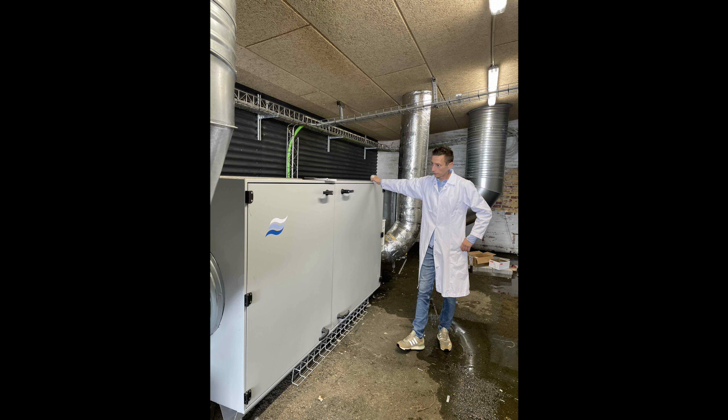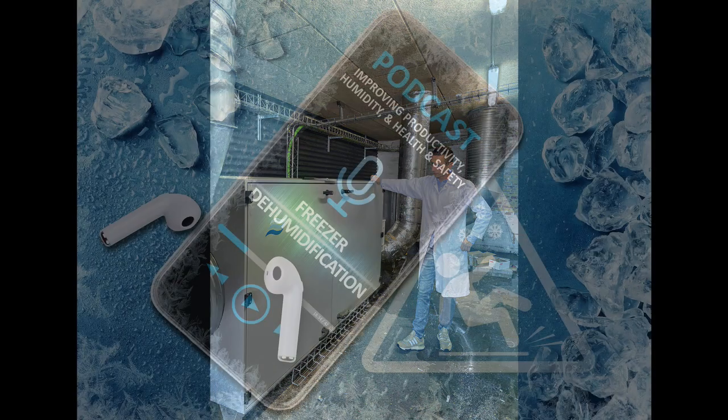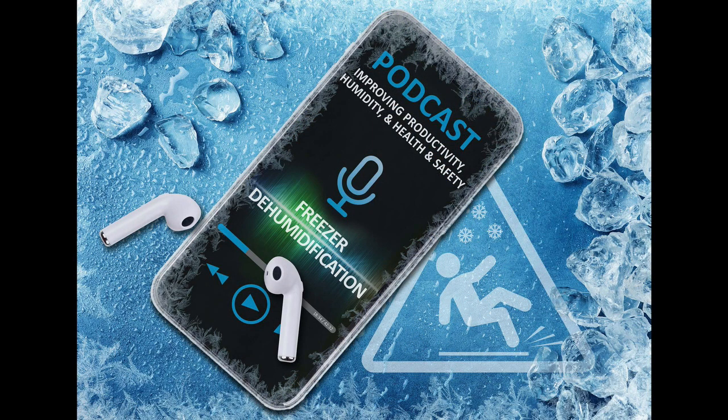Well, there are just so many variables. So how exactly do you do it then? Tell me a bit about the dehumidifier system. Well, how we do it depends largely on the cold store in question and the problems they're experiencing. But in essence, we're trying to deliver the correct volume of air at a low enough humidity, as close to the problem area as possible, to stop, or at least reduce, the issues they're experiencing. So if this is icing by a doorway, we'd be delivering dry air above the entrance from a type of air curtain, so that the dew point, and that's the condition at which moisture condenses, is never reached. So no condensation means no ice. And in fact, whatever ice there is will actually disappear through sublimation.